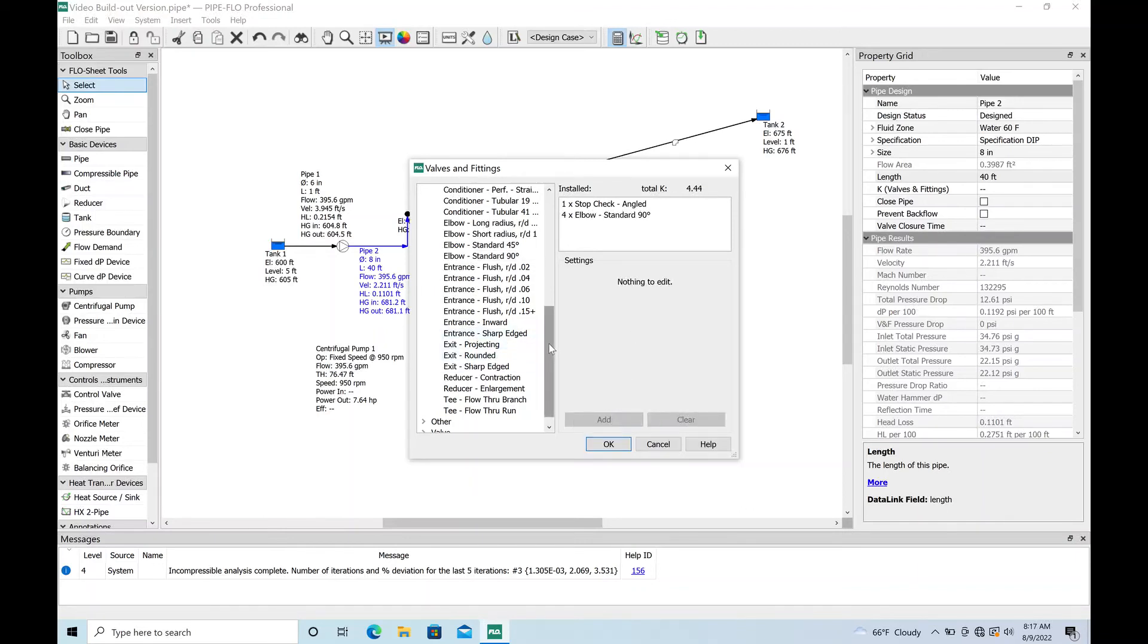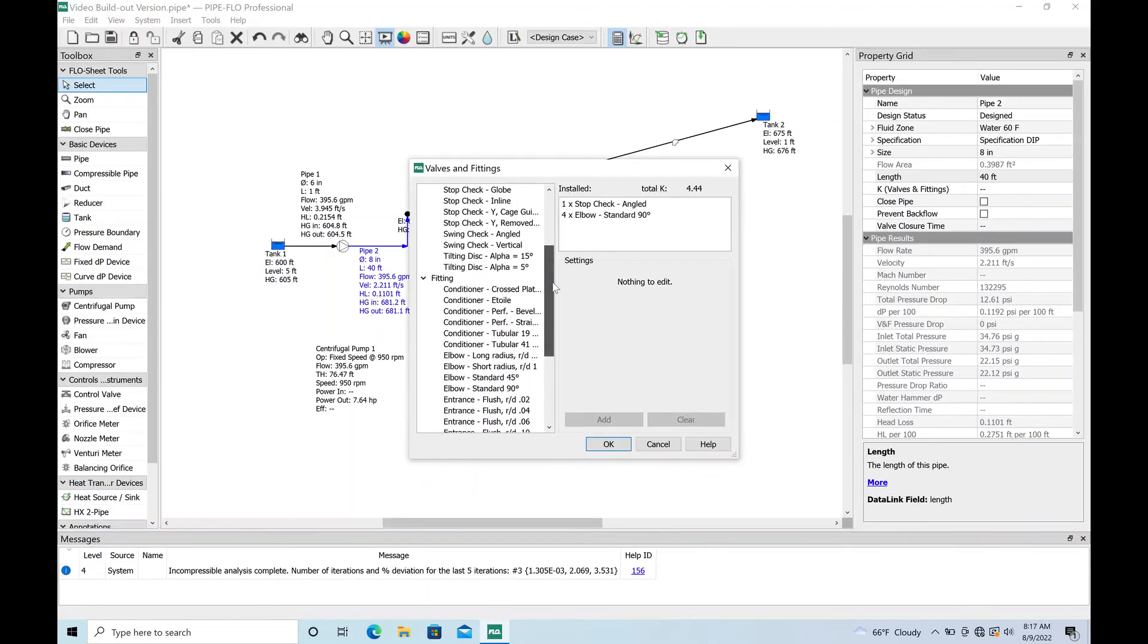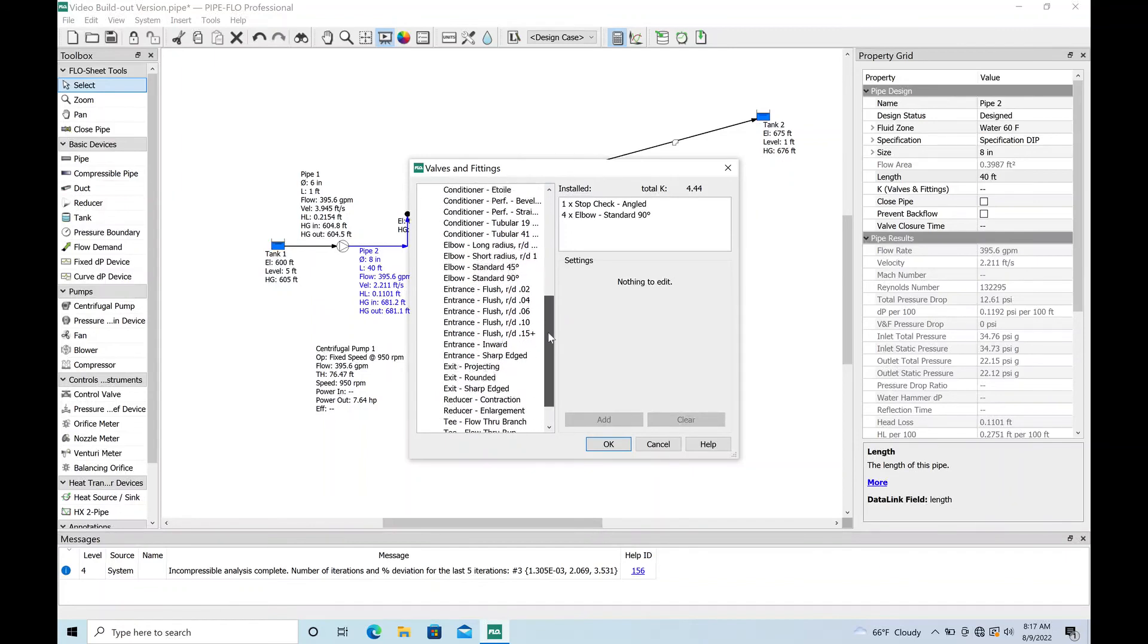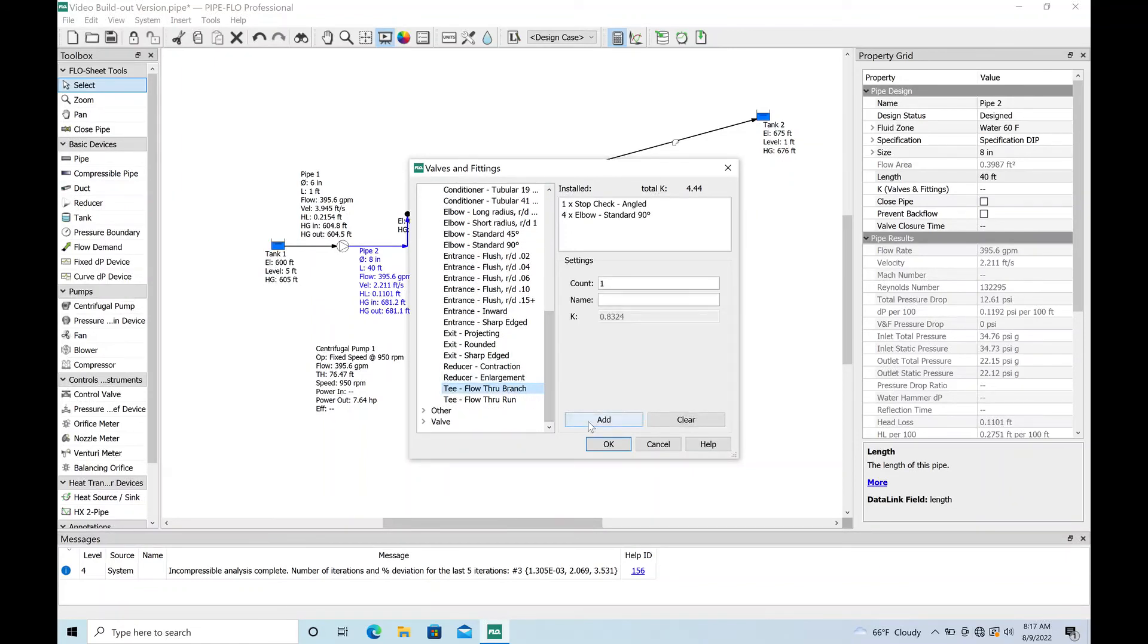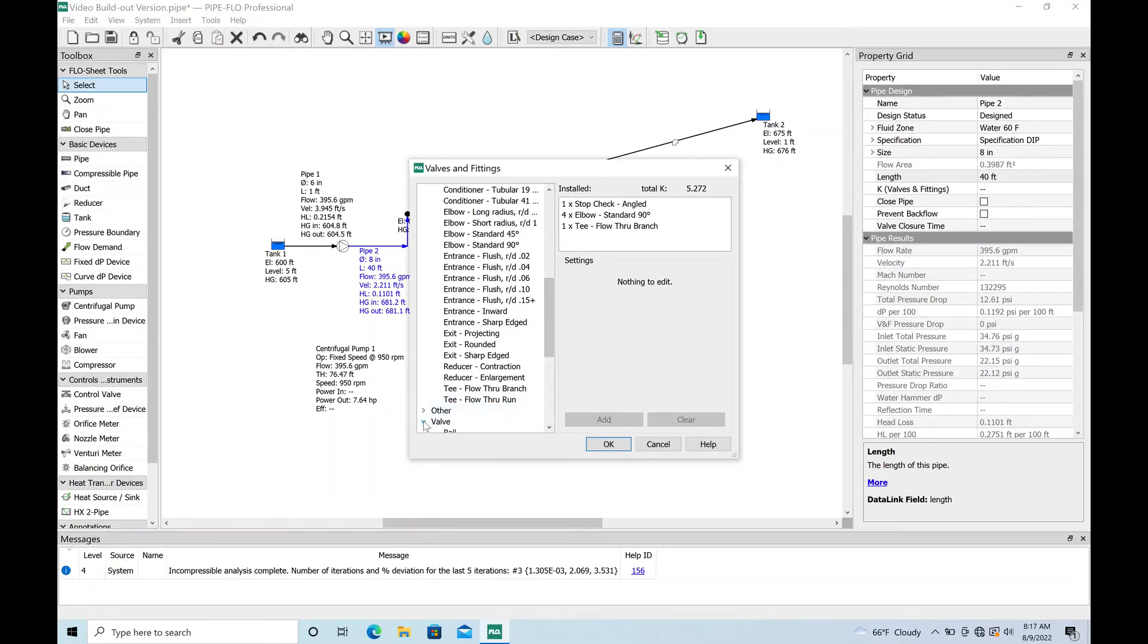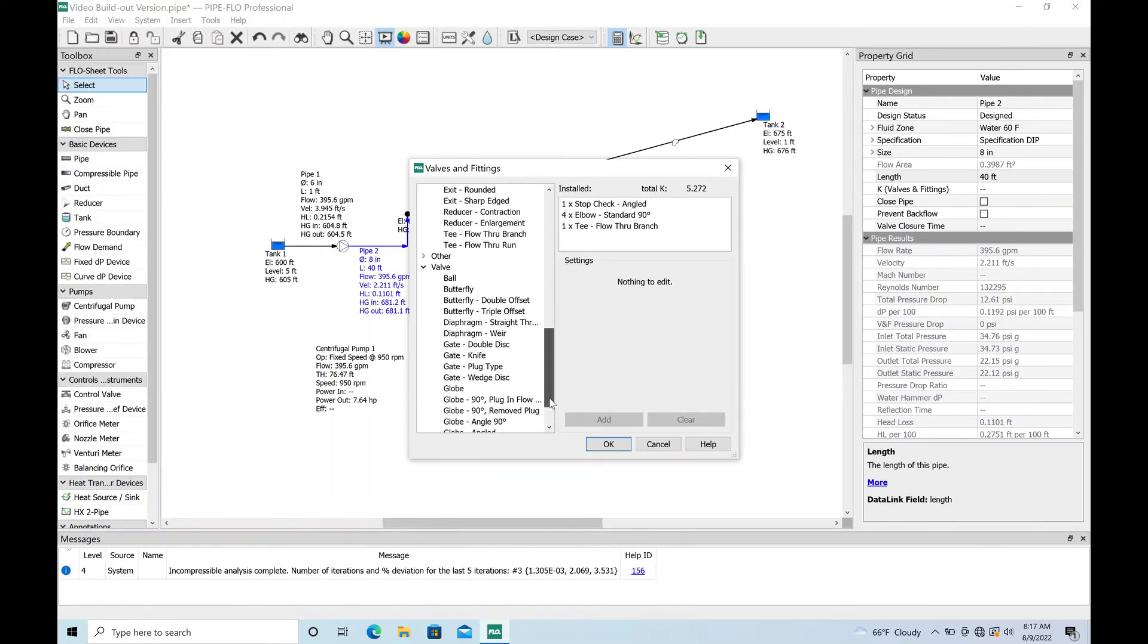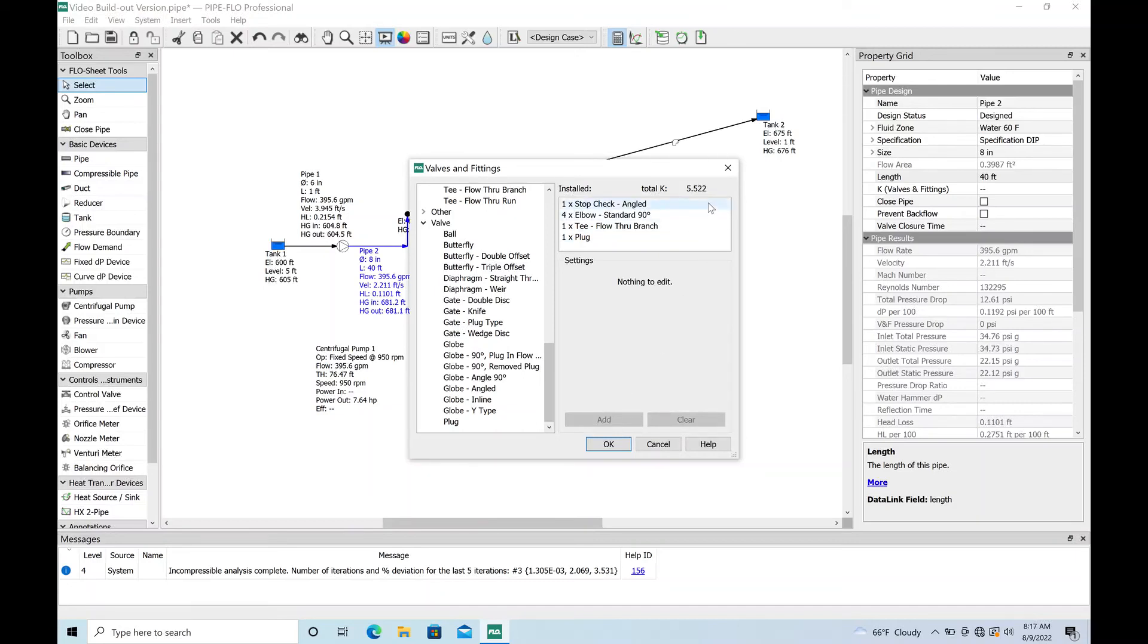Let's see what else are we going to need. You might have a T, a T like a flow through a branch. Going to add one of those in because we're probably going to have two pumps on a pump station like this. Let's see, let's put a plug valve in. Most of the folks that I work with like to use plug valves instead of gate valves on sanitary sewer pump stations. There you go, you've got a pretty good collection of some fittings.